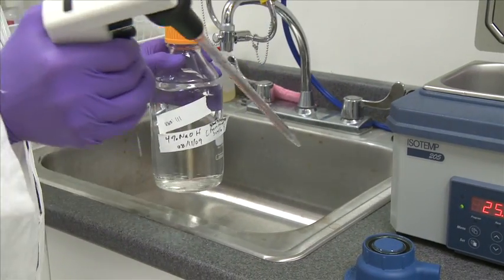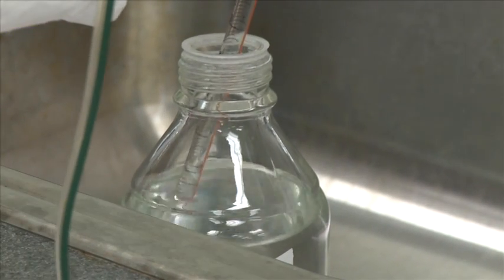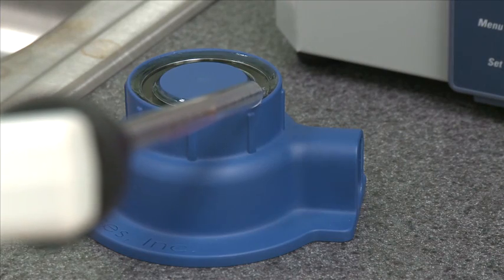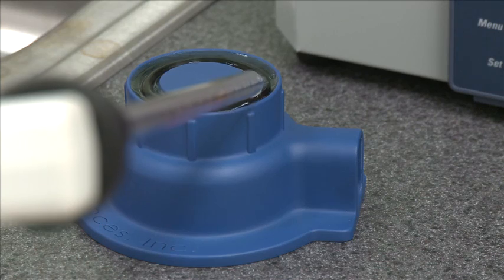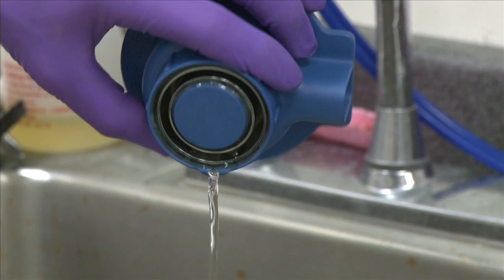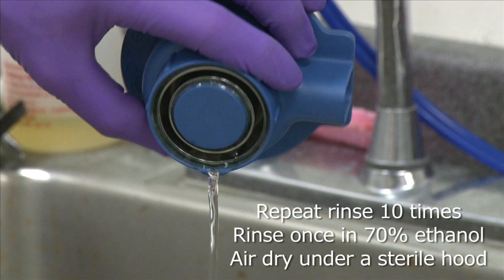Chamber cleaning is necessary to remove biological contaminants and ions. The electrofusion process is sensitive to the presence of ions, so clean chambers are essential to prevent excess ion contamination. The following cleaning process is recommended: immediately after use, rinse the chamber in reagent-grade water. Fill the chamber with 4% sodium hydroxide and soak for 5 minutes. Empty the chamber and rinse in reagent-grade water for 10 seconds. Repeat rinse 10 times. Rinse once in 70% ethanol. Air dry under a sterile hood.